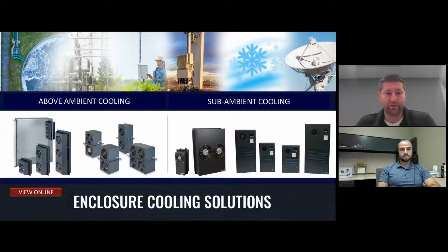You can exchange heat through above-ambient coolers. The one on the left is our heatsink cooler, which relies on circulating air inside the cabinet to collect heat, conducting it through a baffle plate in the middle, with another fan outside to reject heat to ambient air. It's a fairly straightforward, economical solution for customers.